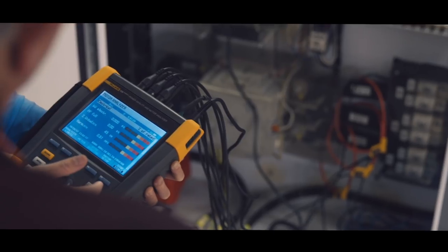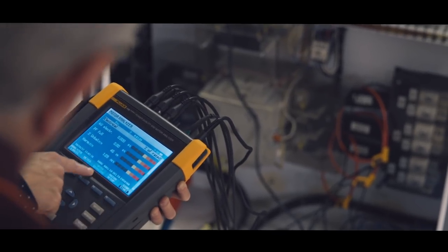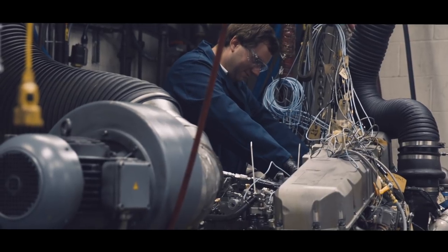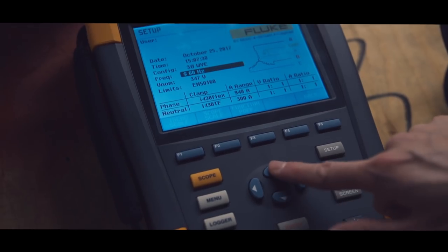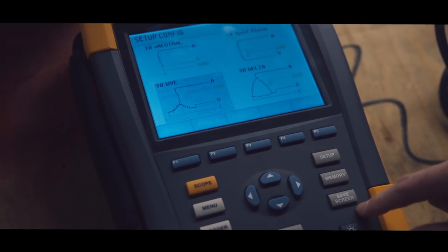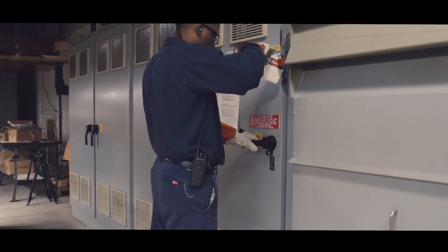We're looking at the torque characteristics of those motors and the dyno drums. Now what we can do is actually put the motor onto the machine tool and verify what we have there and actually fingerprint that machine, making sure that motor's doing what it's supposed to — the torque characteristics. And now we can go back at it at three months and say: where am I? Are we deteriorating? Are we in the same place?